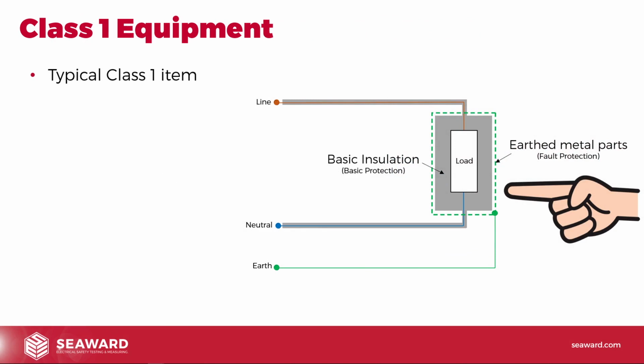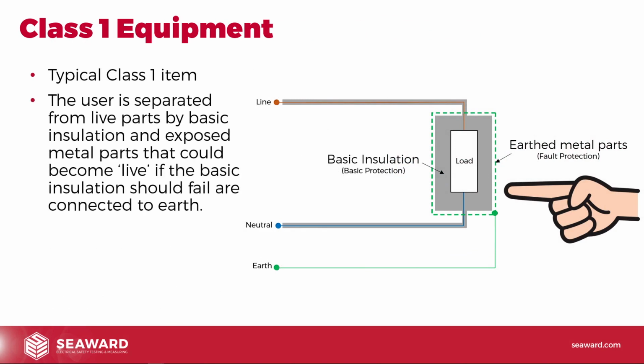So this is a typical item of class 1 equipment. The user is separated from live parts by basic insulation. You can see the grey basic insulation there. And exposed metal parts that could become live if the basic insulation should fail are connected to earth. So you can see there we've got our earthed metal parts. If there's a problem with the basic insulation and the live parts came in contact with exposed metal parts, those parts are connected to earth. So what we've got is really a two-stage process.